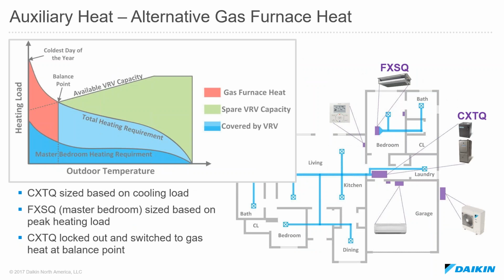So let's take a look at an actual example. The first example we're going to look at is that alternative type of auxiliary heat source. We have a single-story residential floor plan here. We have a gas furnace and an A coil serving the main area of the home. And then the master bedroom is broken off on its own zone. So this master bedroom, that FXSQ, that medium static ducted unit in that master bedroom, is going to have to be sized based off the peak heating load because it doesn't have a secondary source available to it, versus the CXTQ, the A coil, that does. So we only need to size that based off of cooling because we're always going to have the option of switching over to that gas furnace.